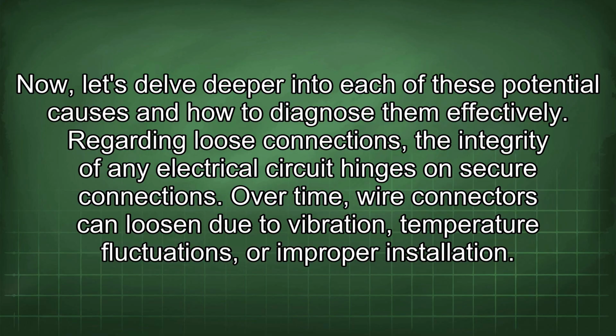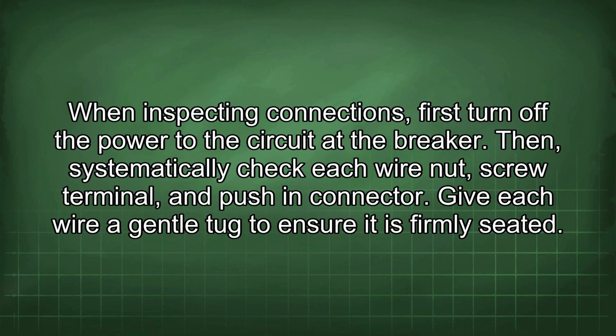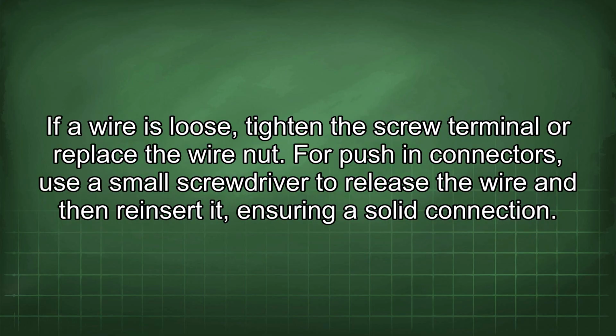Regarding loose connections, the integrity of any electrical circuit hinges on secure connections. Over time, wire connectors can loosen due to vibration, temperature fluctuations, or improper installation. When inspecting connections, first turn off the power to the circuit at the breaker. Then systematically check each wire nut, screw terminal, and push-in connector. Give each wire a gentle tug to ensure it is firmly seated. If a wire is loose, tighten the screw terminal or replace the wire nut. For push-in connectors, use a small screwdriver to release the wire and then reinsert it, ensuring a solid connection.